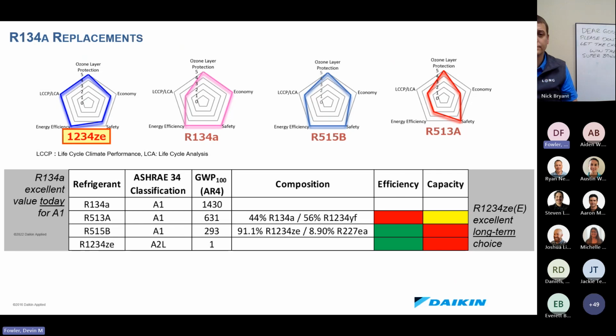Looking at these R134A replacements, there's a few ways that we can classify these. The first is ASHRAE 34 classification, as I just explained. R134A, 513A, and 515B are all A1 classified refrigerants. R134A has a GWP of 1,430. We're now offering R515B with the GWP of 293 for that low GWP refrigerant, and we still do have R513A with the GWP of 631.